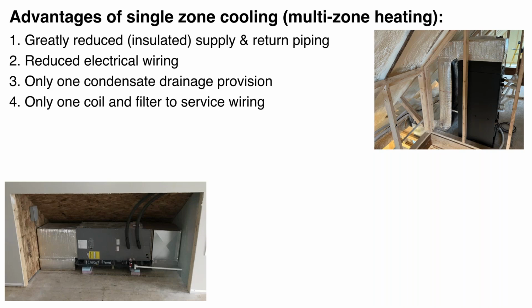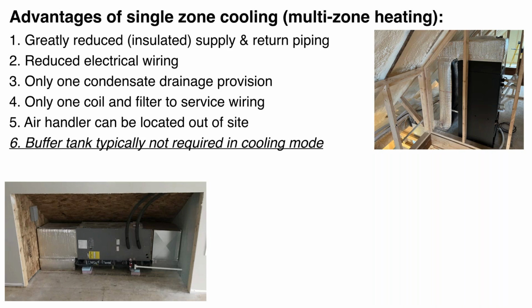You only have one coil and one filter to service. So you have a single point of service as opposed to going around and spraying down each one of these wall-mounted units. Okay, you can locate the air handler out of sight, but accessible. And you don't typically need a buffer tank in a cooling mode if you're matching the coil capacity in your air handler reasonably well to the cooling capacity of the heat pump. Don't put a 2-ton air handler on a 5-ton heat pump. You're simply going to short cycle it.